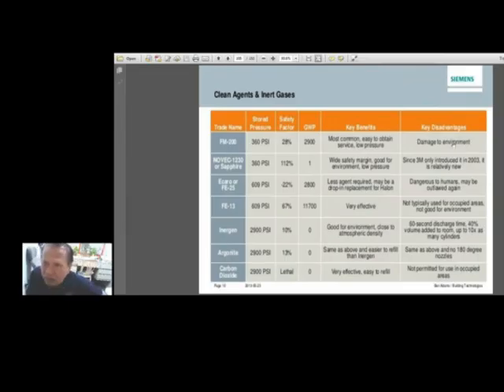Okay. Let's see, Novec. Novec is produced by 3M. So, 360 PSI, 112 safety factor. GWP is 1. Then, wide safety margin, good for environment, and it is low pressure. Since 3M only introduced it in 2003, it is relatively new. Okay.